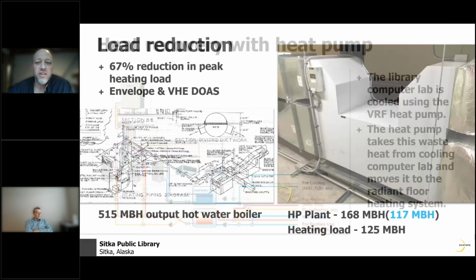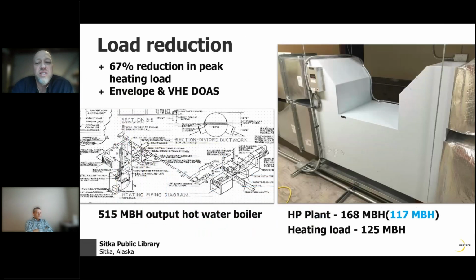The load reduction from the VHE DOAS gave us a significant reduction in peak heating load, and that savings was the mechanism that paid for the rest of the conservation package—the envelope and the VHE upgrade over a regular DOAS system. We saw a significant reduction in the heat plant: the original boiler was 500,000 BTUs, and the new one is around 168,000—a significant savings in first cost.